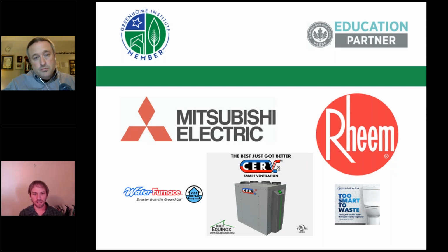Thermostats - without getting into names, what are you looking for, what do you like, what don't you like? If you're going to use modulating equipment, you're basically looking at top of the line manufacturer-based thermostats. Because if you put, say, a Nest or an Ecobee or some other more simple thermostat on a modulating piece of equipment that can have 100 different speeds, now it only has 2. That's dumb, don't do that. Put on a control that can control every capability the equipment has. And all the controls suck in one way or another - they all have weaknesses, so it's never good enough.